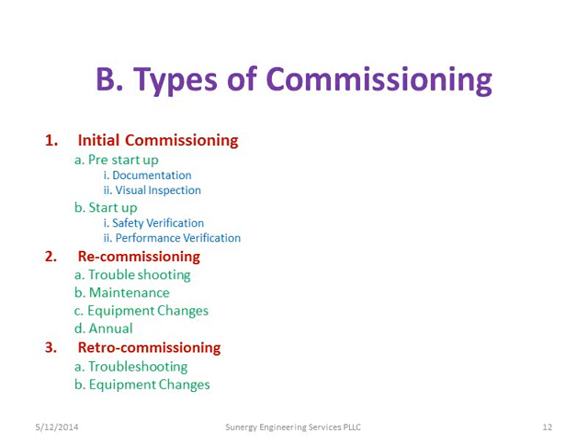The one I really hate is retro commissioning. That's when someone calls you up and says, it's not working, can you come and figure it out, because nobody else knows why it's not working. That's usually the hardest one because you have no records - no records of the initial install, no paperwork, no drawings. So it becomes a real troubleshooting nightmare.